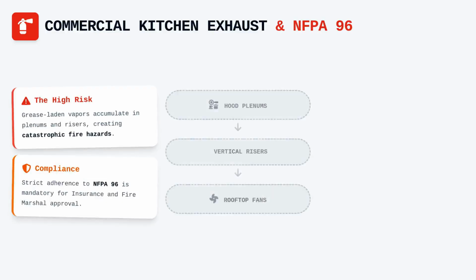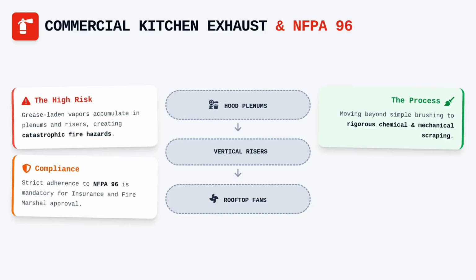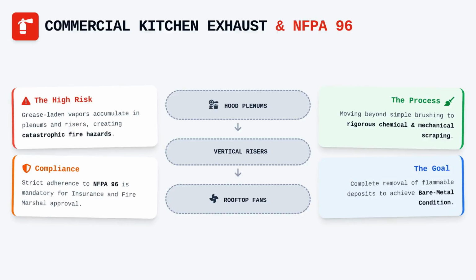You have to remove flammable deposits from hood plenums, vertical risers, and rooftop-mounted fans to prevent catastrophic duct fires. NFPA 96 dictates the clearance, access panels, and cleaning frequencies required to keep these systems within the bounds of insurance and fire marshal compliance. When cleaning these systems, you are not just brushing surfaces. You are often performing a rigorous chemical and mechanical scraping process to return the metal to bare metal condition.